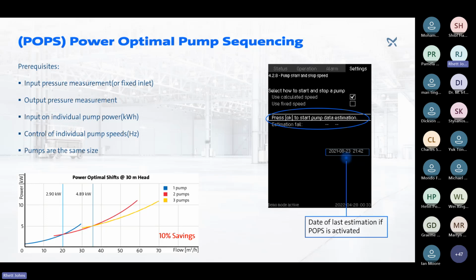The problem with this is that you're not running the pumps at the best efficiency point of those individual pumps. With speed-based sequencing, the pumps cannot be guaranteed to run at the optimal power, since the system is only running based off of speed. Using power optimal pump sequencing, you actually program in the characteristics of your pump and the curve of the pump for each pump in your system. And using that, the multi-pump controller is then able to run each individual pump at the best efficiency point of that pump per the flow required.